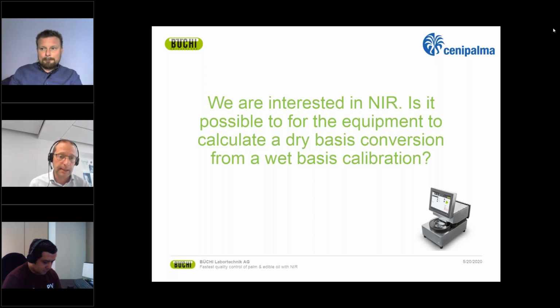With the ProxiMate, there's a built-in function that allows dry weight conversions. When you set up an application within ProxiMate, you can choose an as-is or dry basis option, and there are a number of built-in moisture options, such as 10, 13, or 14% moisture. If some other type of conversion is needed, it's possible to set that up manually using the calculated properties parameter, where a user can add their own equation to work on the output of the calibration.